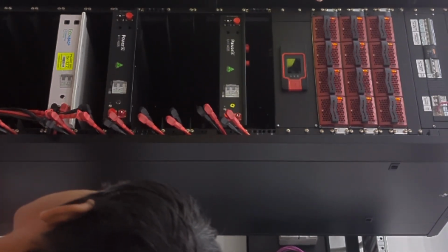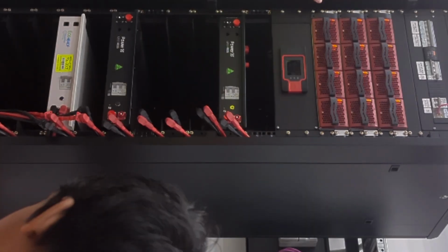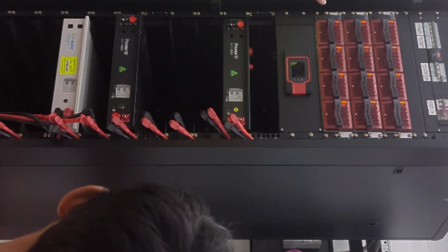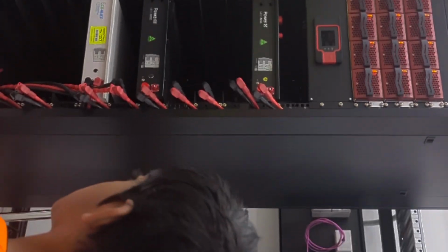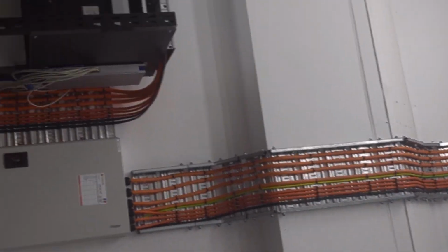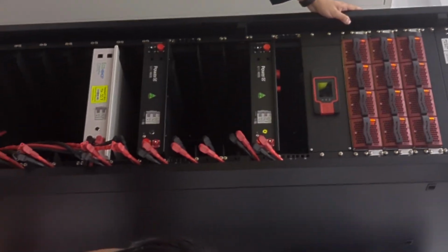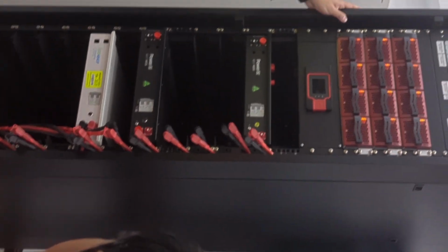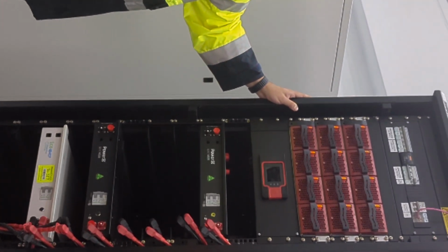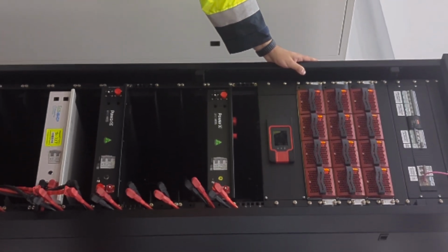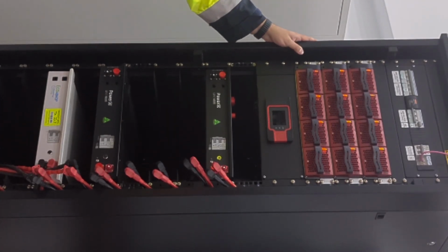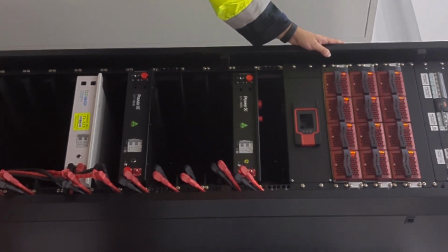I think the biggest one in the country is about 500 kilowatts or so, 460. 460 kilowatt output, a megawatt of storage. Megawatt of storage, and up to 2 megawatt hours on that one. And 7 ton of copper to get 48 volts up to 450 kilowatts. So it makes sense scaling to say 2 or 3 of the cabinets, even 4. You could scale to 32 of them if you really, really want to, if you love the solution.